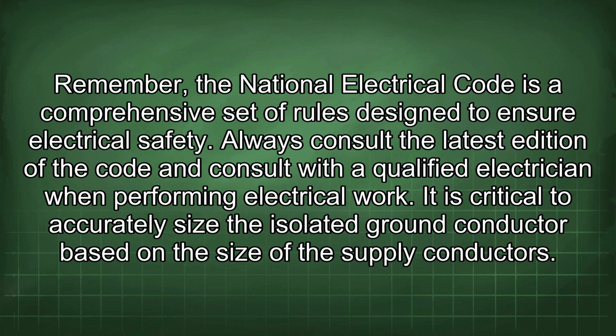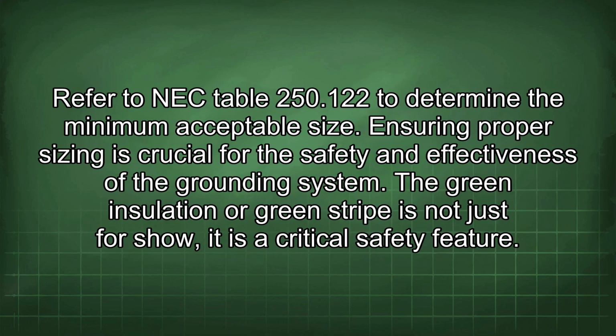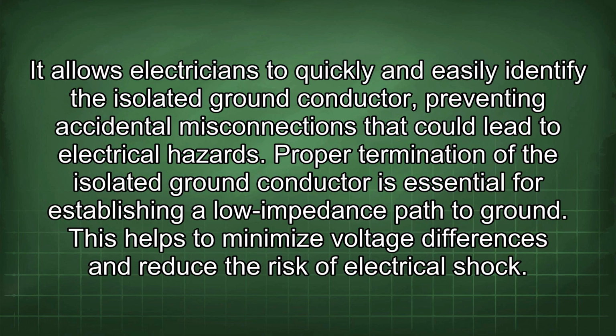It is critical to accurately size the isolated ground conductor based on the size of the supply conductors. Refer to NEC Table 250.122 to determine the minimum acceptable size. Ensuring proper sizing is crucial for the safety and effectiveness of the grounding system. The green insulation or green stripe is not just for show, it is a critical safety feature. It allows electricians to quickly and easily identify the isolated ground conductor, preventing accidental misconnections that could lead to electrical hazards. Proper termination of the isolated ground conductor is essential for establishing a low impedance path to ground. This helps to minimize voltage differences and reduce the risk of electrical shock.